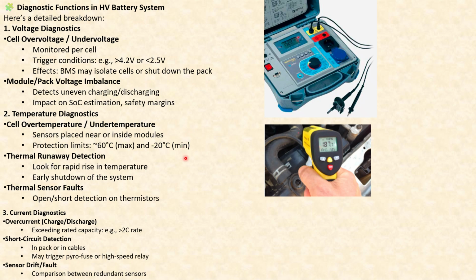And when it comes to thermal runaway detection, look for a rapid rise in temperature and early shutdown of the system. All right, now considering thermal sensor faults: open and short detection on thermistors. To proceed further, what are the current diagnostics? When it comes to current diagnostics, overcurrent comprises charge or discharge exceeding rated capacity, if it is greater than 2 C rate, and short circuit detection in the pack or in cables, which may trigger a pyrofuse or high speed relay. Also, when it comes to sensor drift and fault, a comparison between redundant sensors.